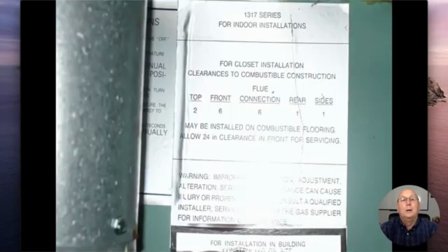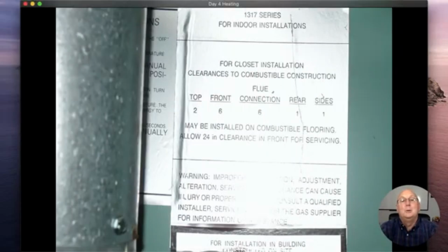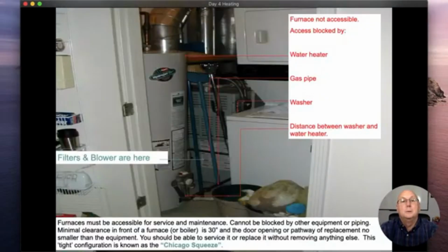Here's another one, same thing: sides 1 inch, back 0, front 6 inches, 6 inches around the vent or the vent connector, and the top again 1 inch. All right, I just want you to know what all those numbers are for. Top 2, front 6, vent 6, rear 1, side 1. Different furnaces have different clearance issues with combustibles. All right.